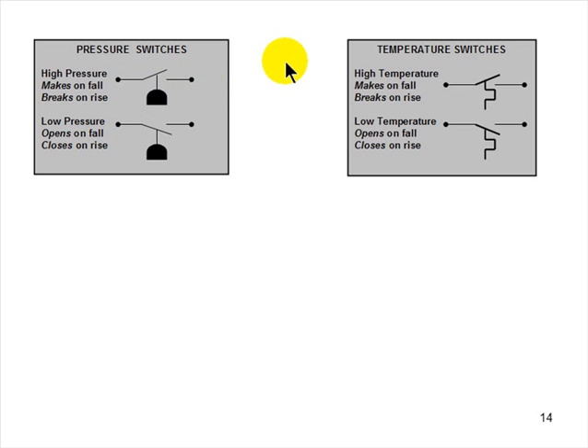This is in series with a contactor coil on your condensing unit. When the pressure in the condenser gets too high, it's going to open up. Save it. You know here that when the pressure gets too low, this switch is going to open up and save the compressor from low pressure. These are temperature. Picture this. This is a bimetal element. It's metal, okay? And if this were held down tight and you heated up this element, this would expand. It would open up. And the switch is above the line, so it's high temperature. This switch is below the line, so it's low temperature. Okay? This is a low temperature switch. You might use it for pump down or something. Or maybe not. Okay?